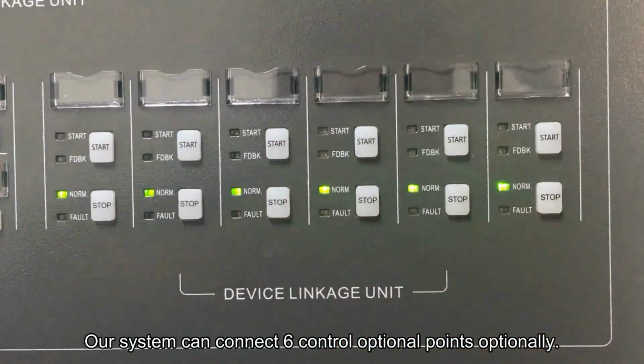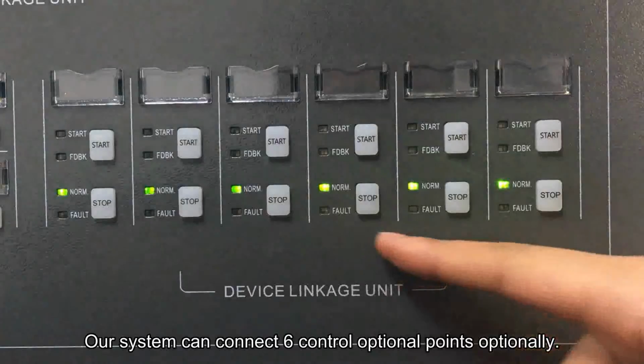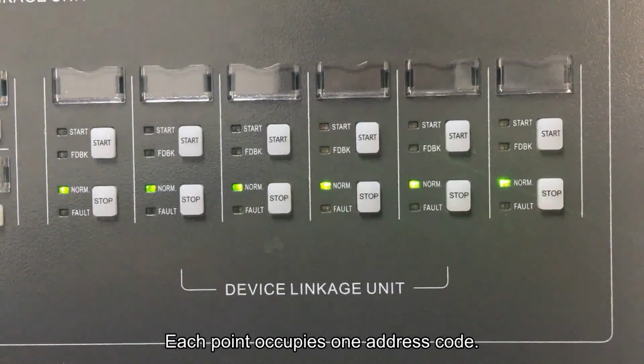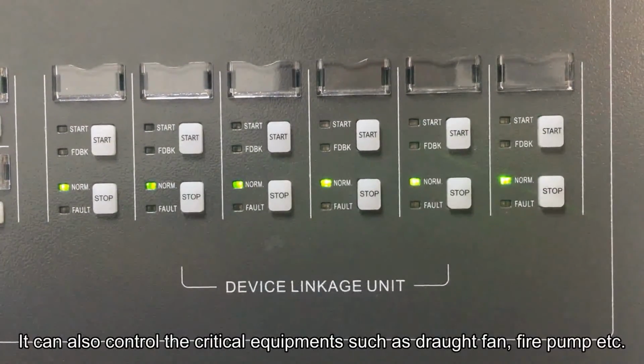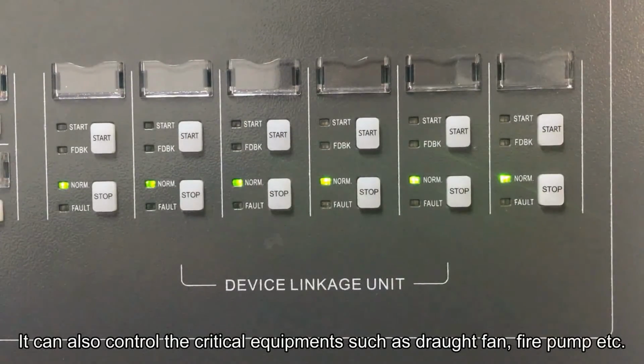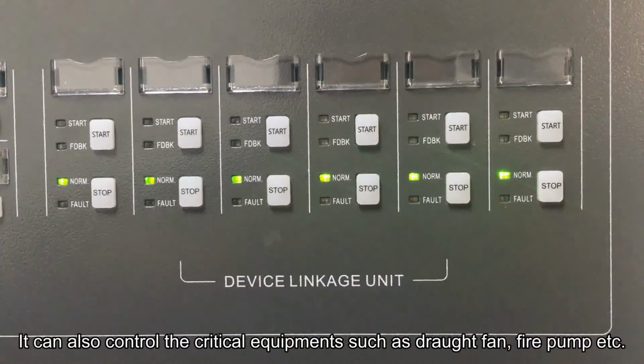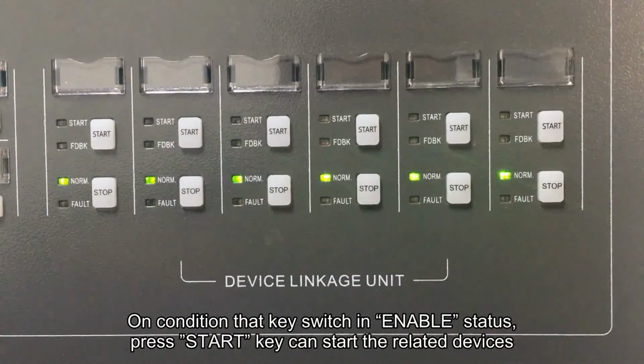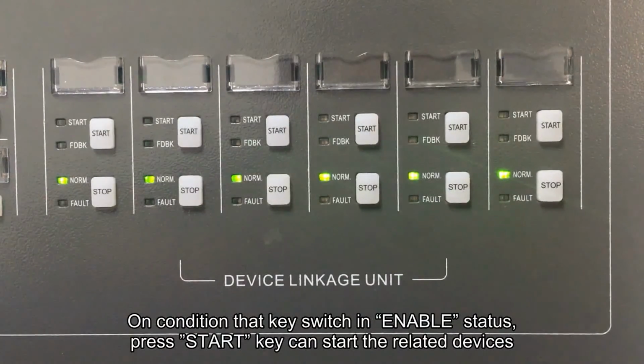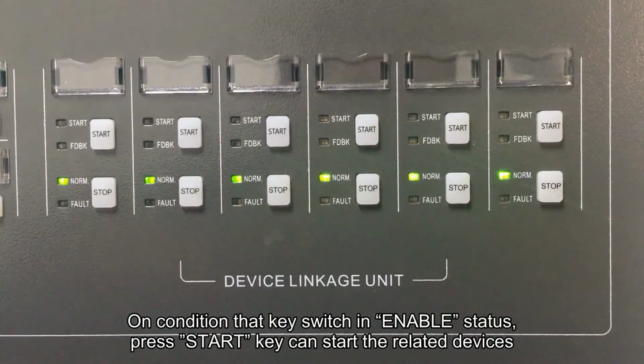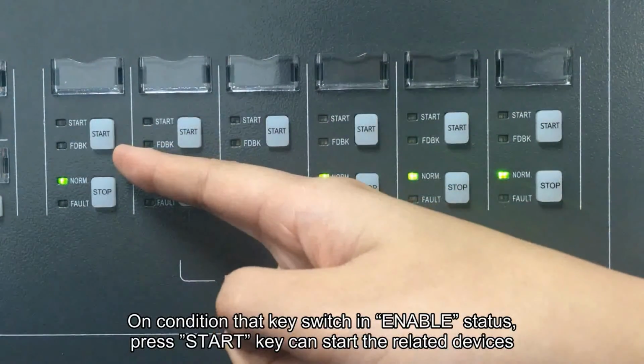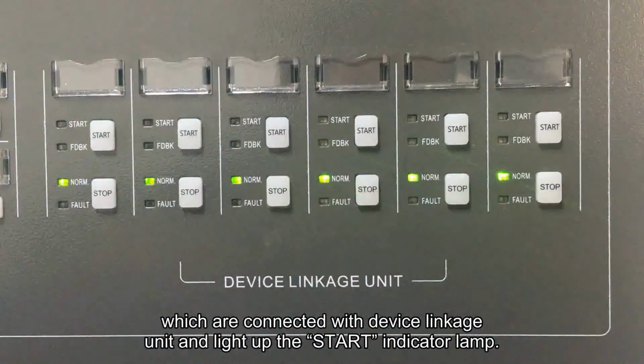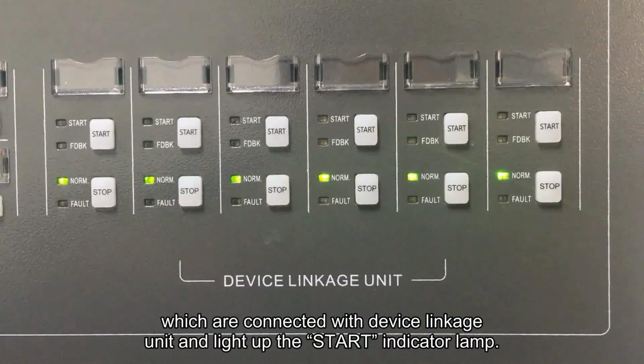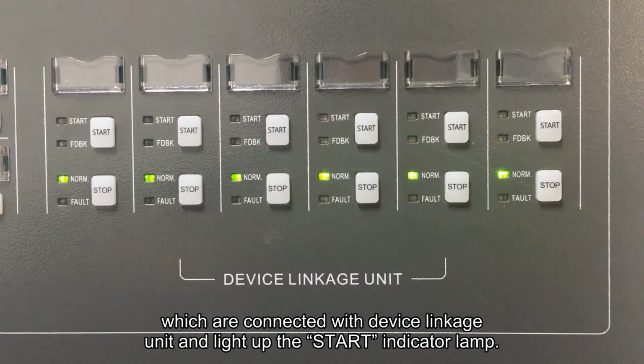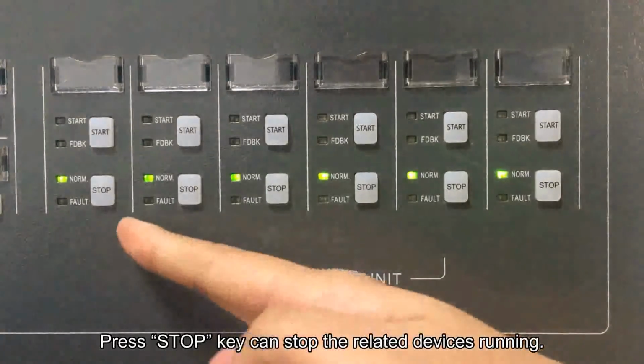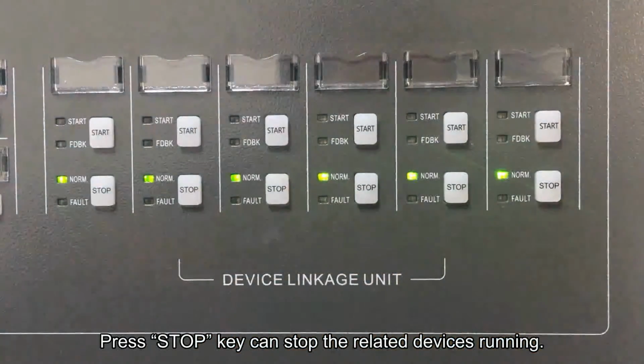Our system can connect 6 optional control points. Each point occupies one address code. It can also control the critical equipment such as draft fan, fire pump, etc. On condition that key switch in enable status, press start key can start the related devices which are connected with device linkage unit and light up the start indicator lamp. Press stop key can stop the related devices running.